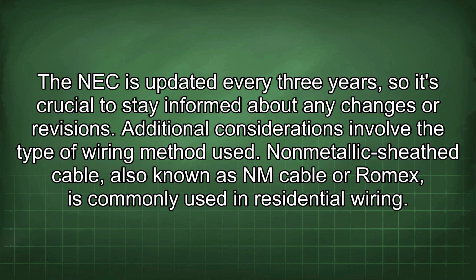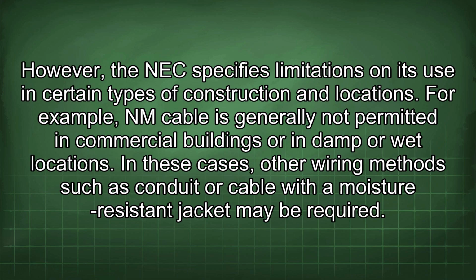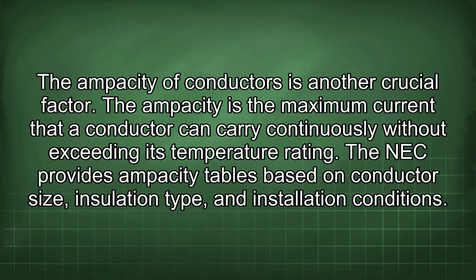Additional considerations involve the type of wiring method used. Non-metallic sheath cable, also known as NM cable or Romex, is commonly used in residential wiring. However, the NEC specifies limitations on its use in certain types of construction and locations. For example, NM cable is generally not permitted in commercial buildings or in damp or wet locations. In these cases, other wiring methods such as conduit or cable with a moisture-resistant jacket may be required. The ampacity of conductors is another crucial factor.